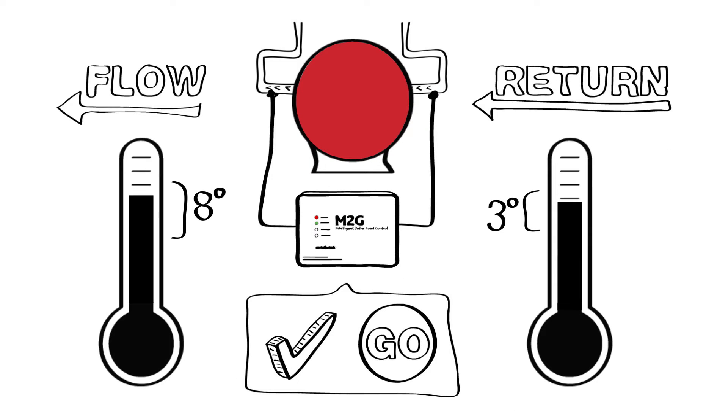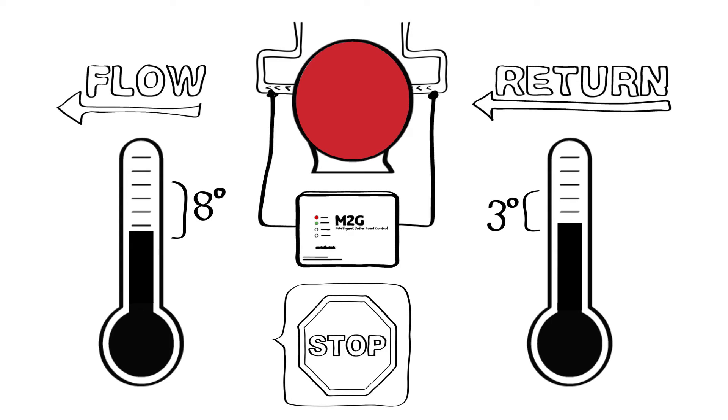If the boiler's temperature gradually decreases in the flow and return and they remain within the dead bands, the M2G recognizes this as natural heat loss and not a real demand. It won't allow the boiler to fire unless the flow drops 8 degrees or the return drops 3 degrees below the initial snapshot reading. The maximum period M2G can prevent the boiler firing is 15 minutes.